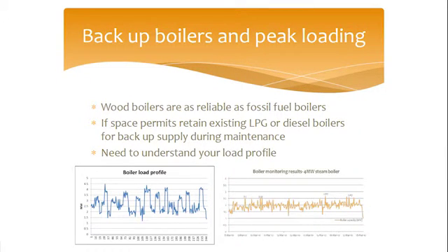Can you use that same boiler for peak loading? I think it all comes down to what your load profile is. This system here, you probably wouldn't. You'd probably design this system for a 2.5 megawatt wood boiler. But with this one here, if your load profile is quite up and down and quite jumpy, then you may want to consider, can I use that diesel LPG boiler for taking on that peak, and I design a base load wood boiler for getting that base load.